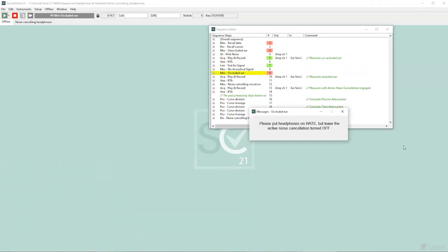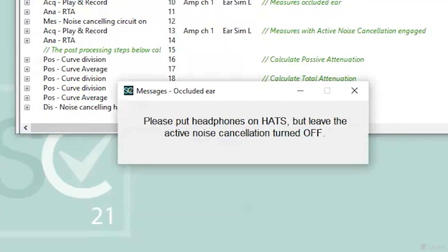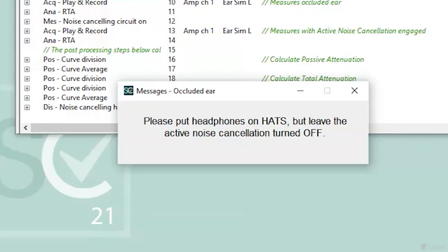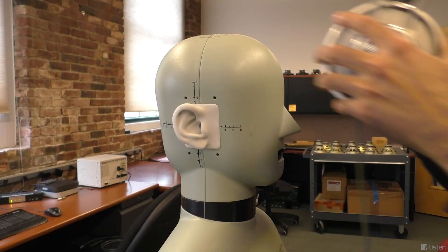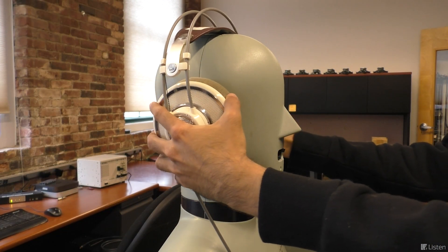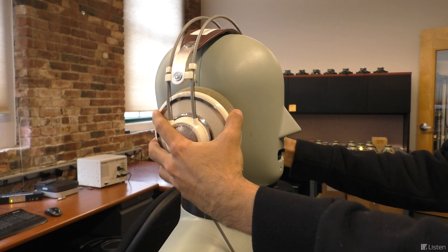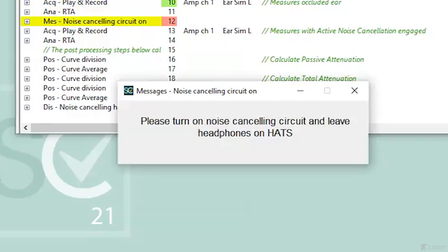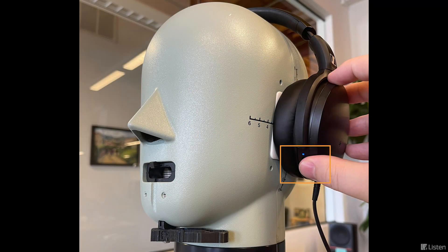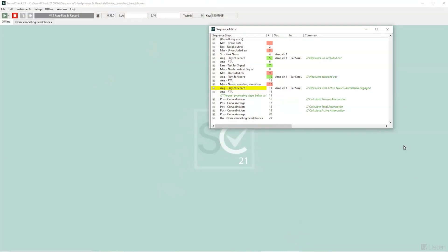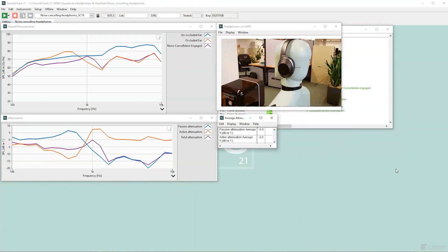Next, the sequence pauses while the operator places the headphones on the HATS, then makes the occluded measurement. The sequence again pauses for the operator to enable the headphone's active noise cancellation, and the third measurement is taken and the results are calculated.